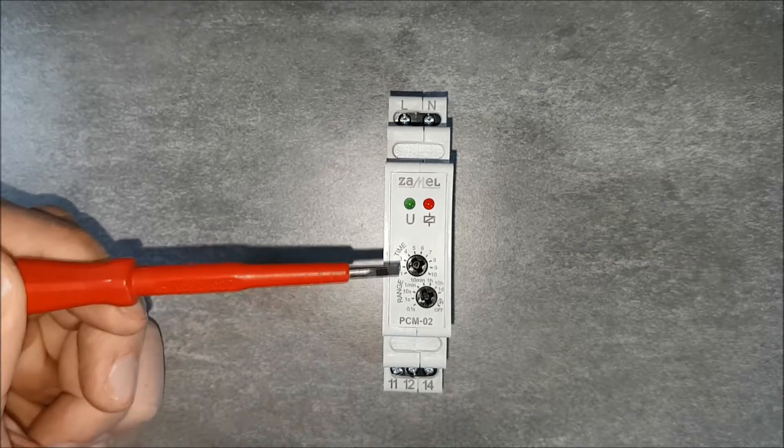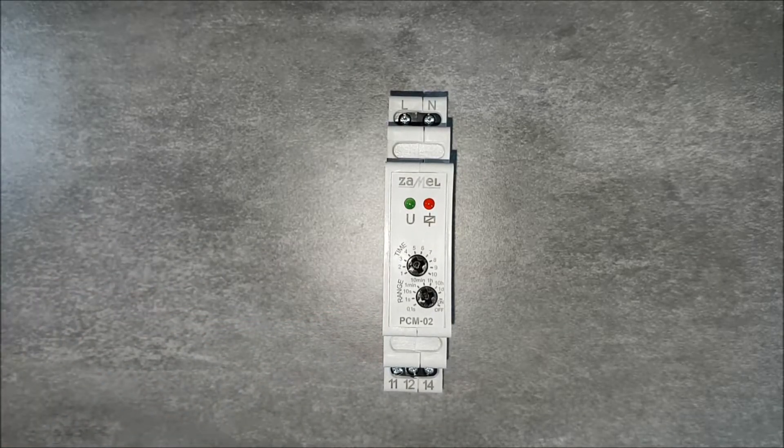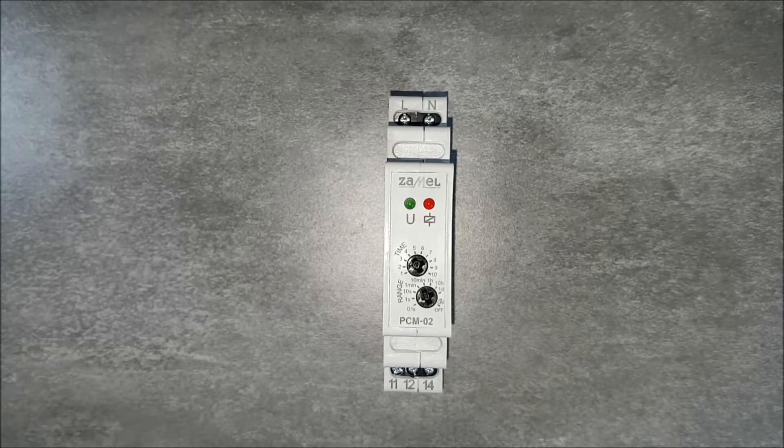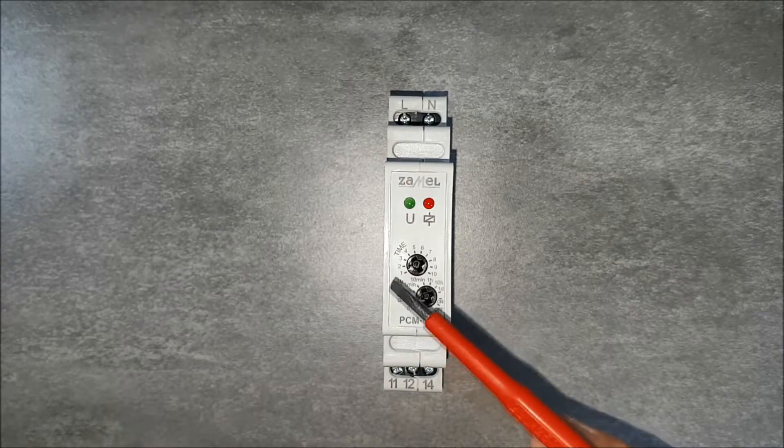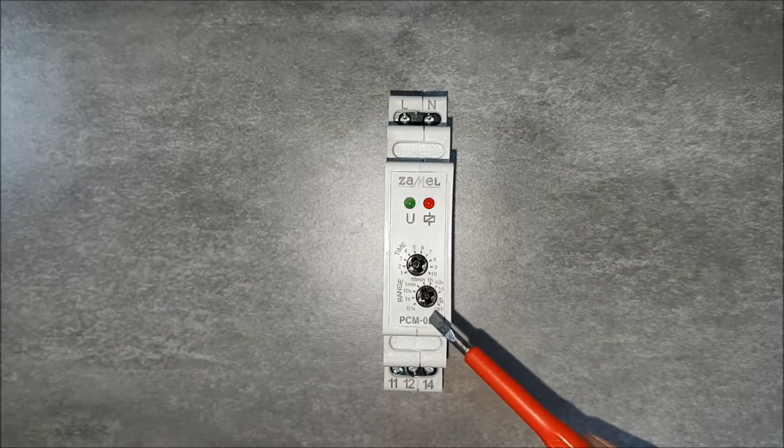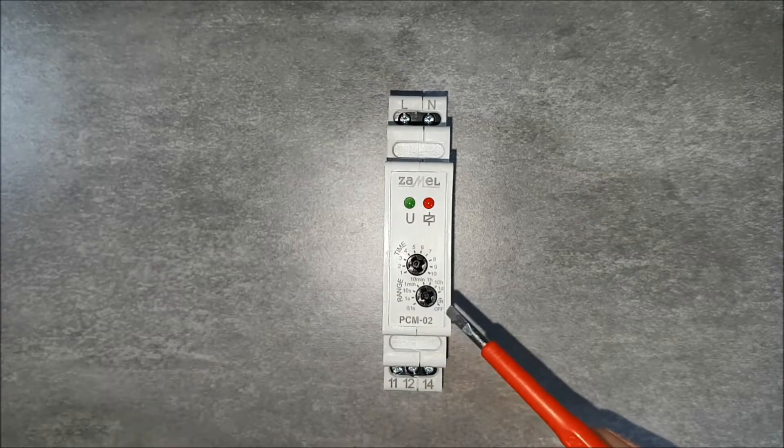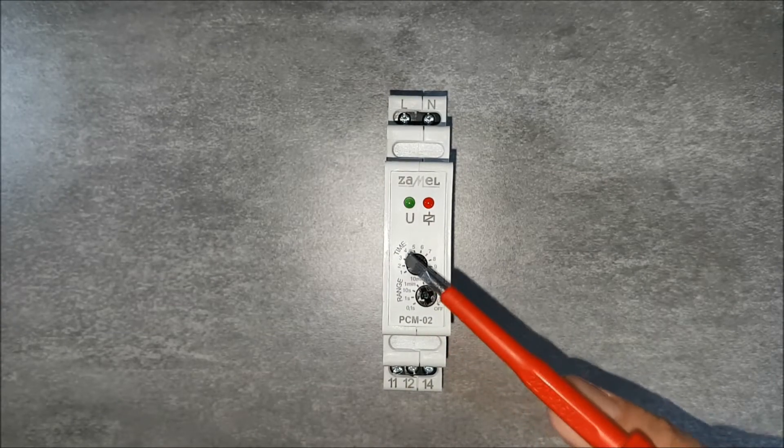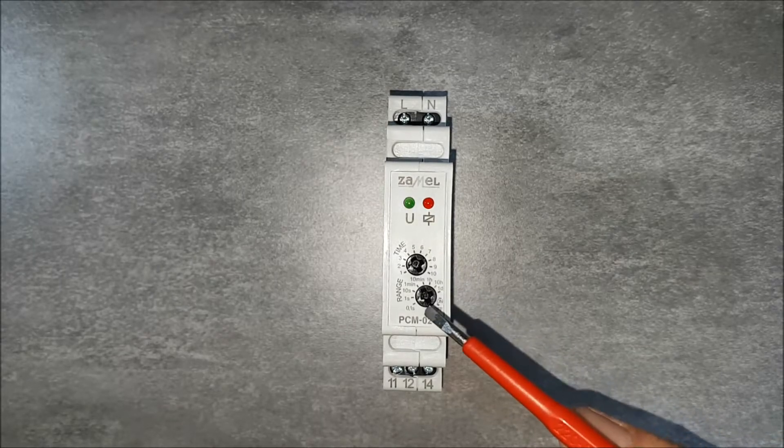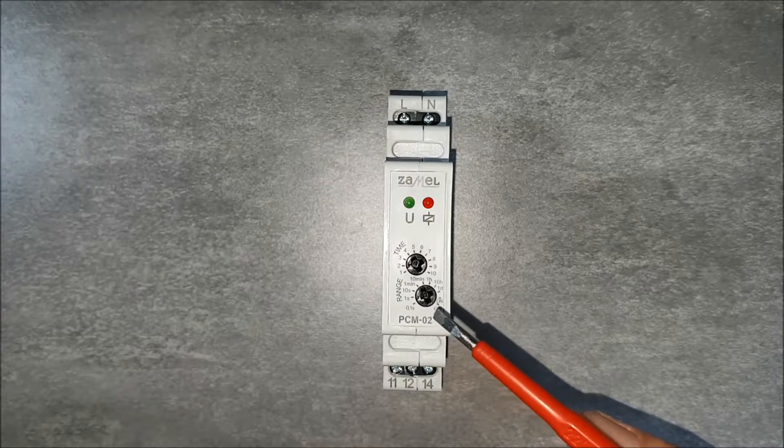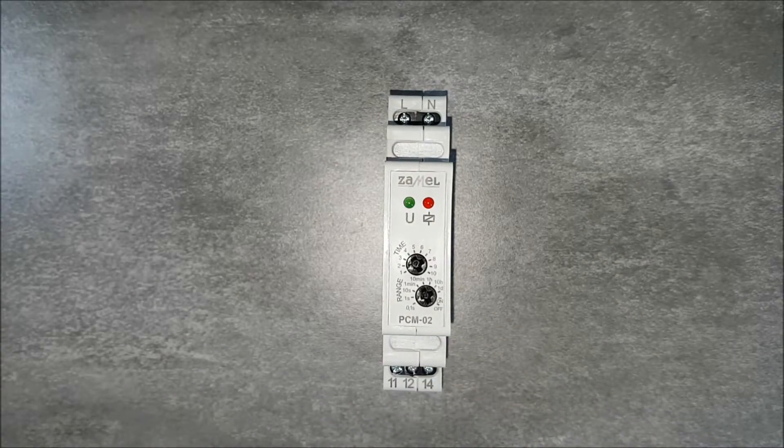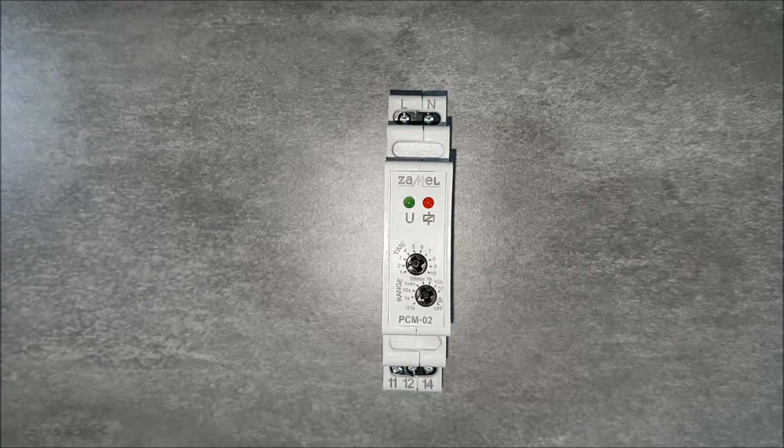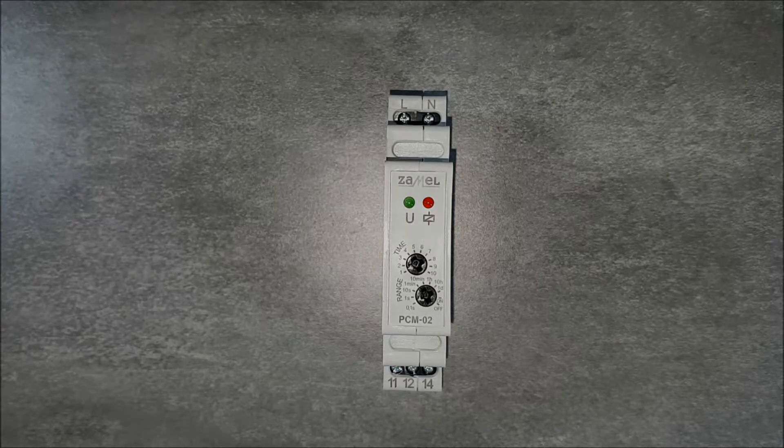There are also two potentiometers. They are for implementing time settings. The lower potentiometer, marked as range, is the base for the calculated time. The upper potentiometer, marked as time, is the multiplier of the value selected on the first potentiometer marked as range. The maximum current capacity of the built-in relay is 16 amperes.